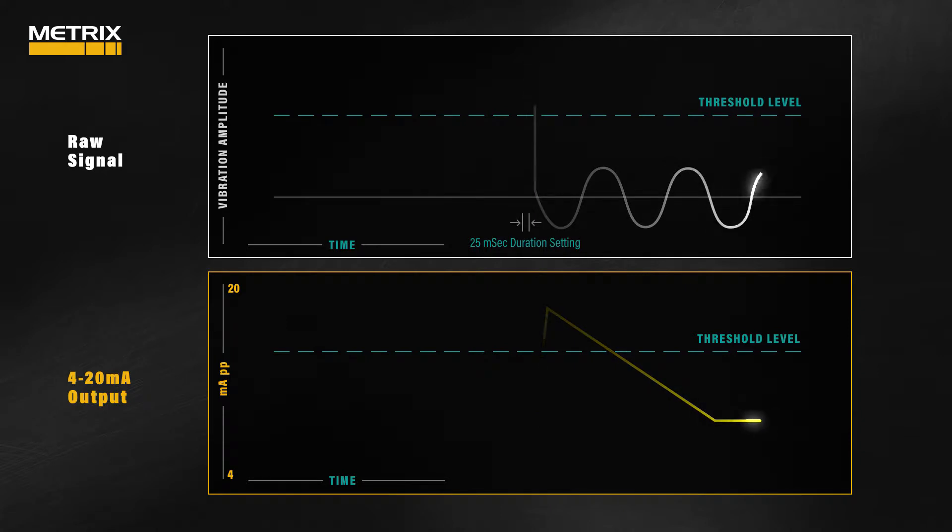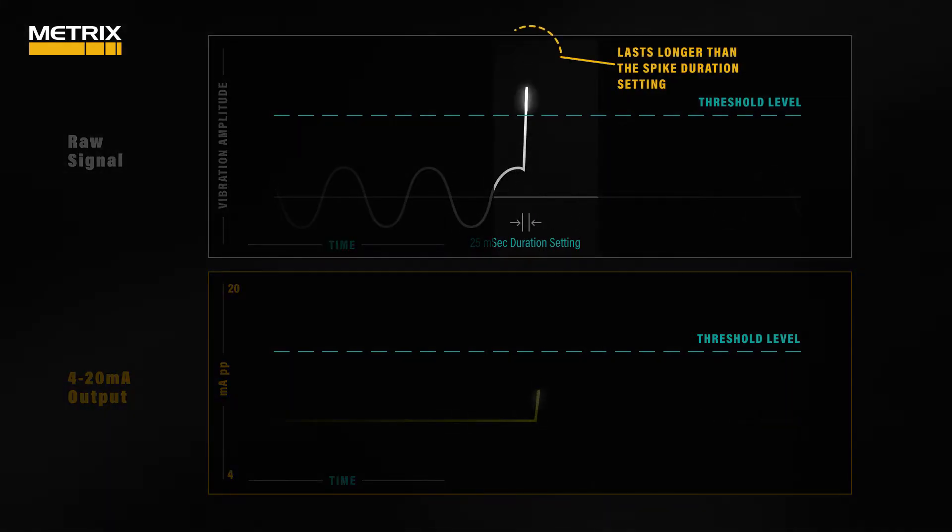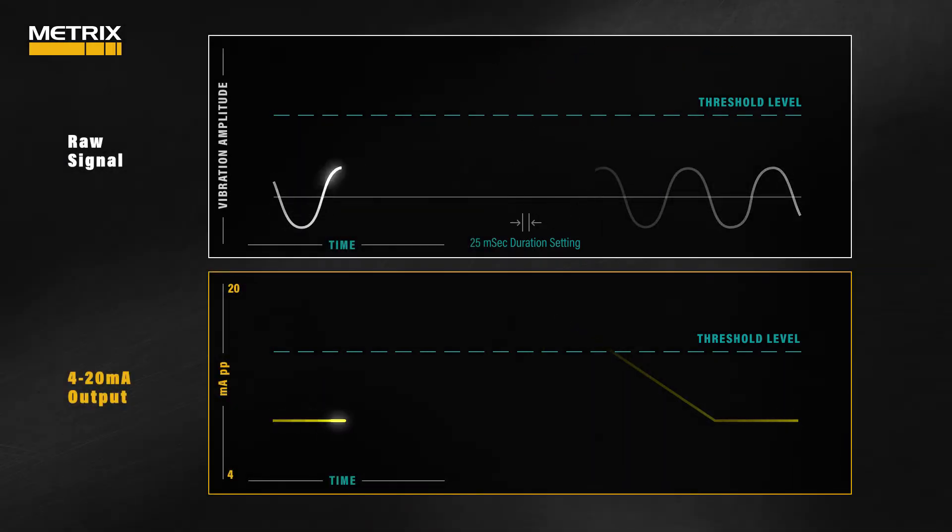Vibration amplitudes greater than the spike suppression setting that last longer than the spike duration setting will be reported normally via the 4 to 20 milliamp output.